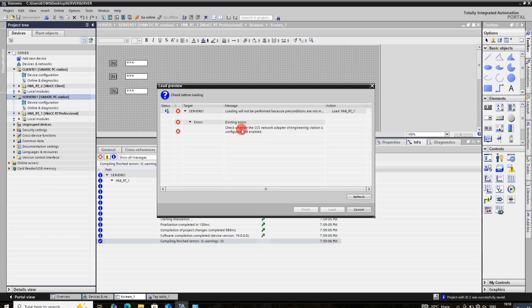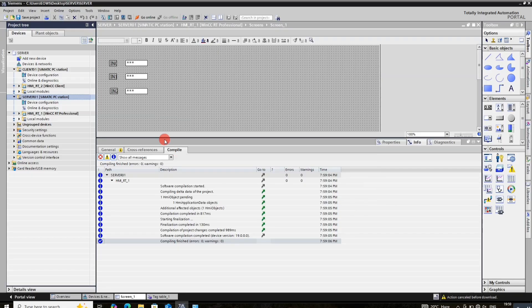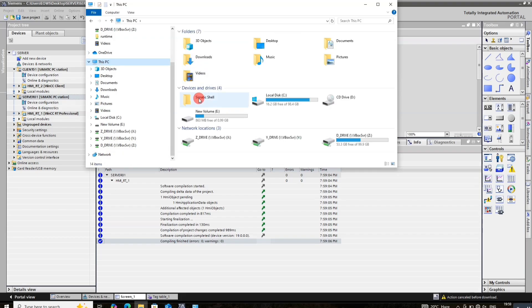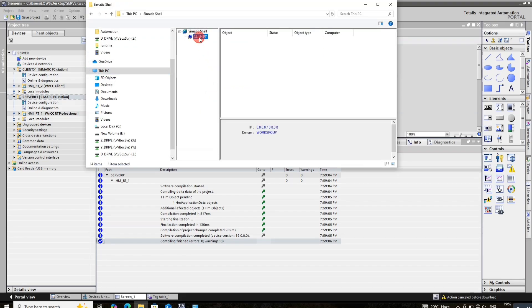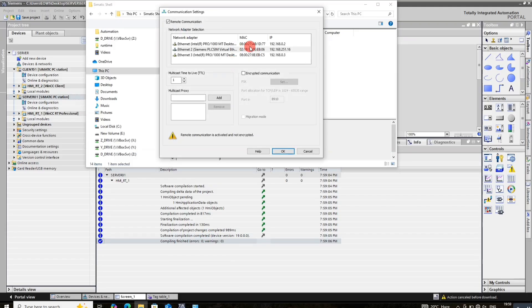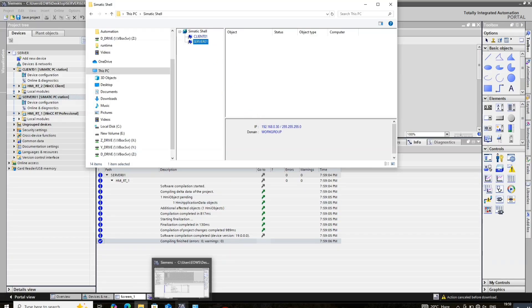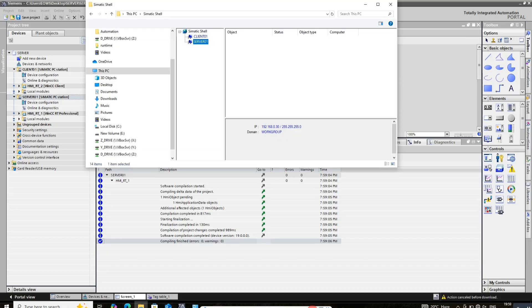There are some errors. This error comes because the terminal bus is not configured on both computers, so we need to configure the terminal bus. Right-click here, go to settings, and select the terminal bus. Press OK — the server computer is now showing in the Simatic Shell.